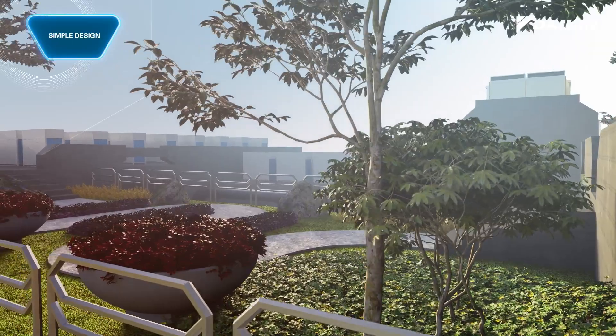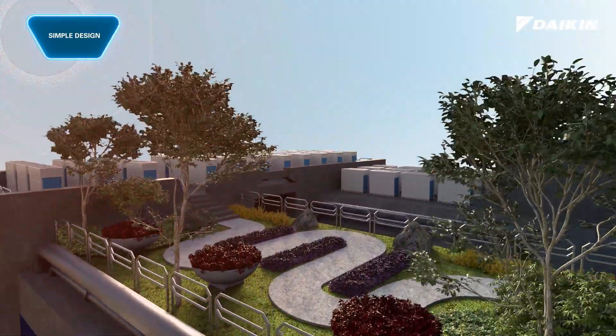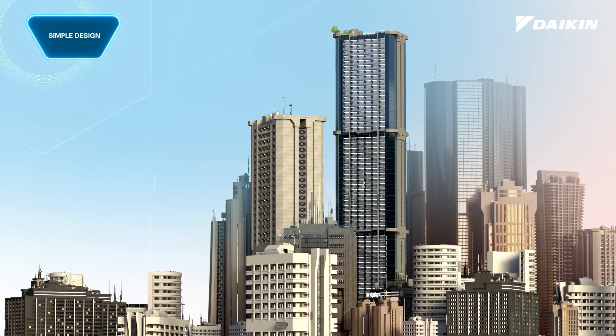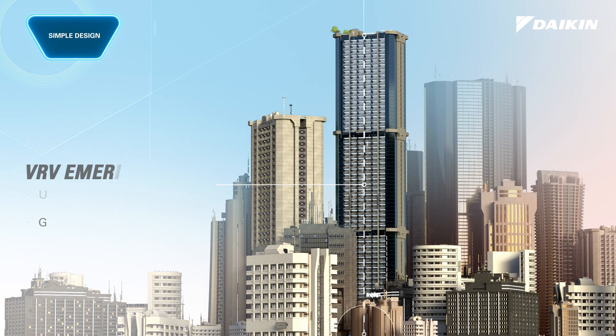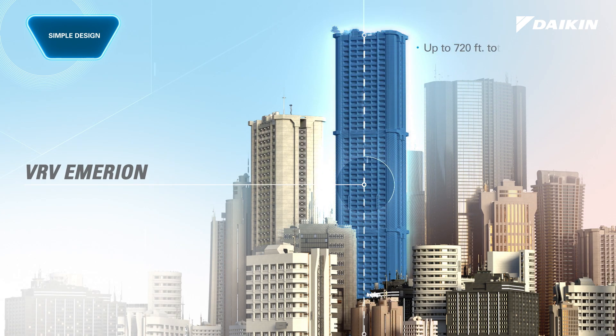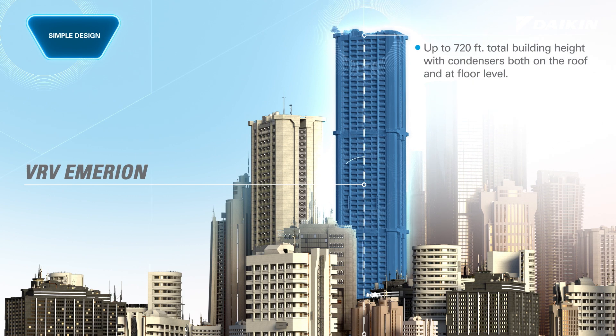Along with space savings, VRV Emerion offers the opportunity to reduce total project costs by reducing the number of modules and the number of electrical and piping connections. By leveraging Daikin's increased piping lengths, the new design allows up to 361 feet of vertical separation, equivalent to approximately 30 floors, and provides opportunities for outdoor units to be centrally located. This opens opportunities to now address buildings up to 720 feet, equivalent to approximately 60 floors, when units are placed both on the roof and base of the building.